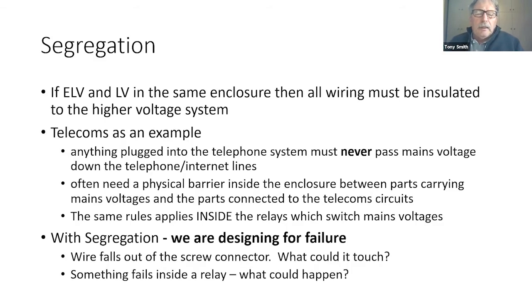There's a fundamental rule that says if you have extra low voltage and low voltage terminals in the same enclosure, you actually need to insulate everything to the highest voltage. So it would mean all your insulation, all your wiring and everything would have to be at mains voltage levels. That's quite often not practical.